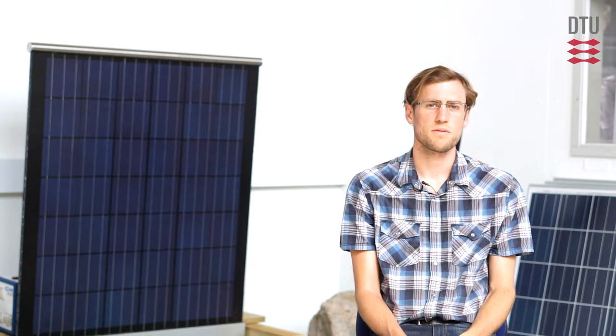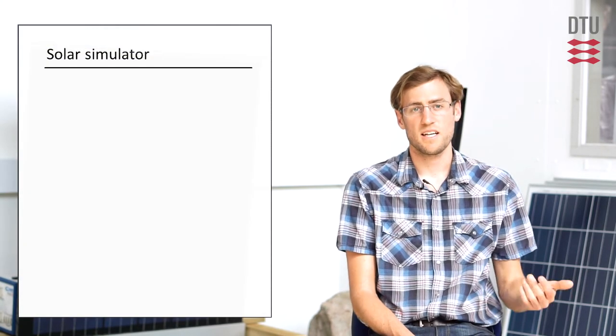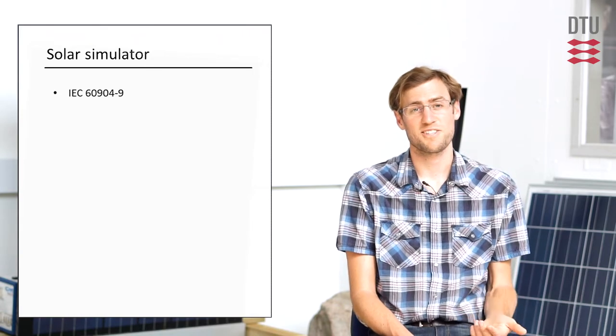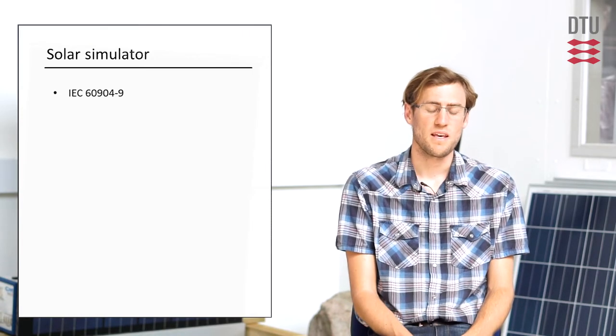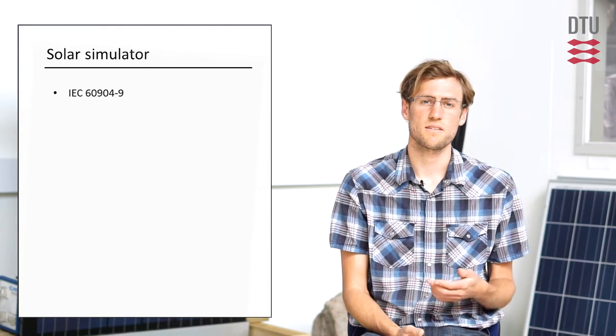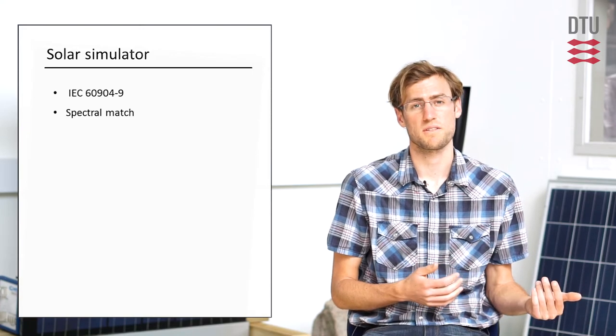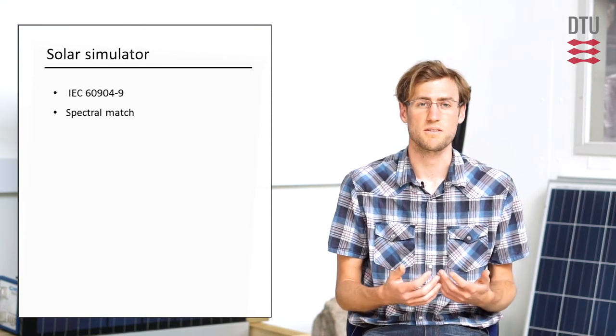There are published standards that describe different criteria that are important when choosing or analyzing the solar simulator. It's outlined in an IEC standard called IEC 60904-9, and there are three criteria that we look at. The first one is the light source's spectral match to the outdoor reference spectrum.